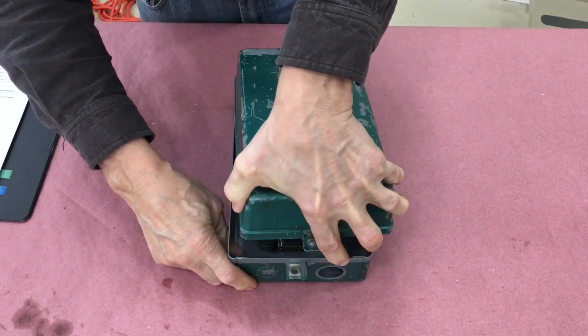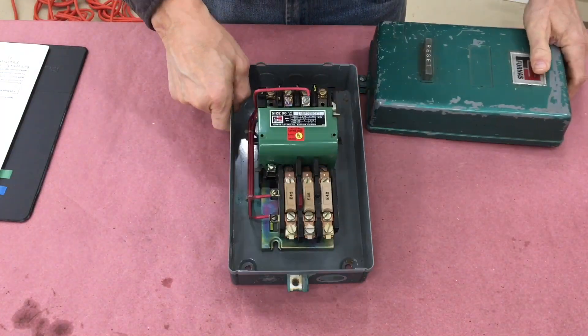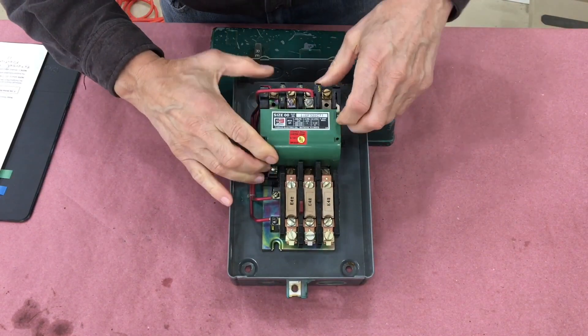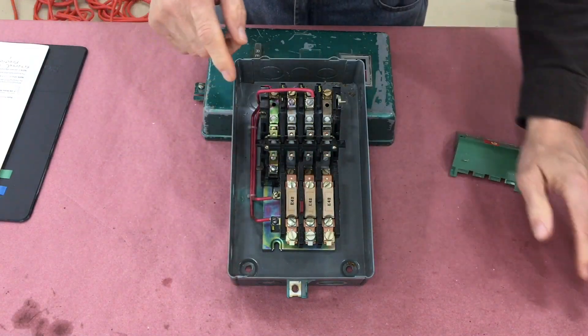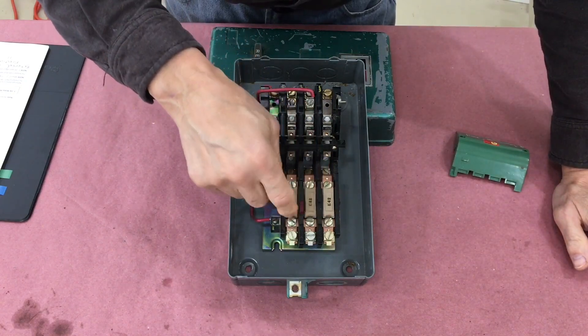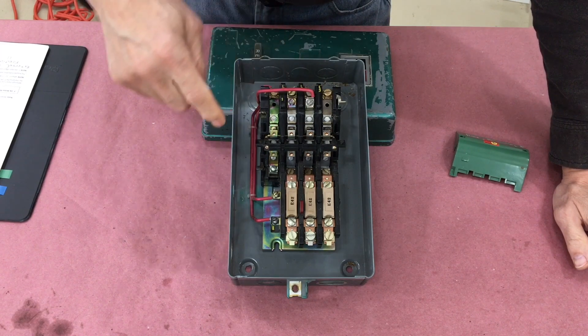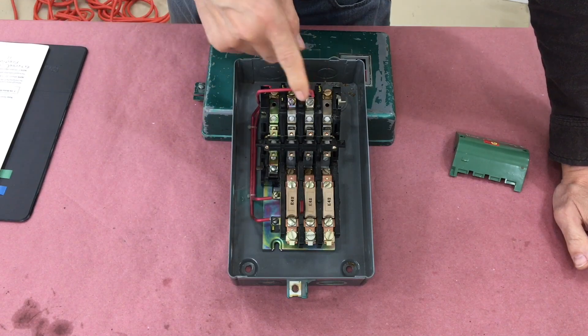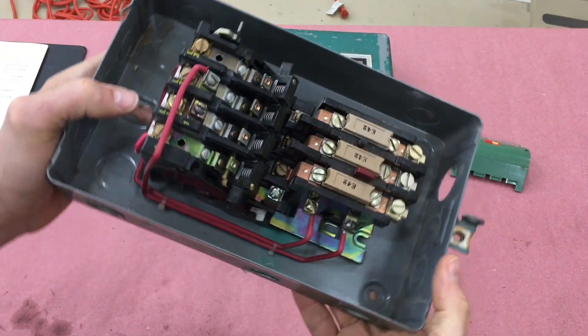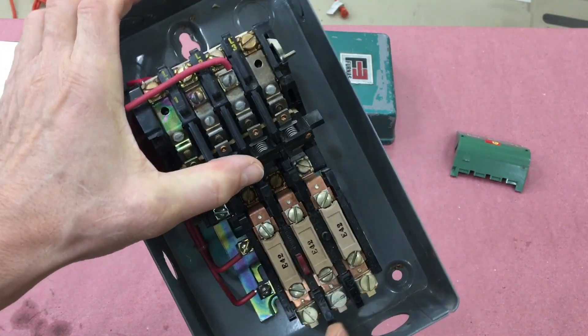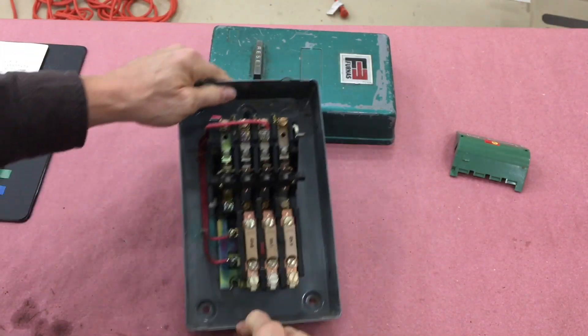This is the main three phase switch box and also contains a relay. It's set on the back of the machine. This is a cover for the relays. The three phases of three phase power came in right here and this is the relays that operated that three phase switch. One of the three phase legs was used as a control circuit and it operated that relay. Here you can see a closer view here. The relay was operated and it switched all three phases at the same time. All of this was replaced by the VFD.